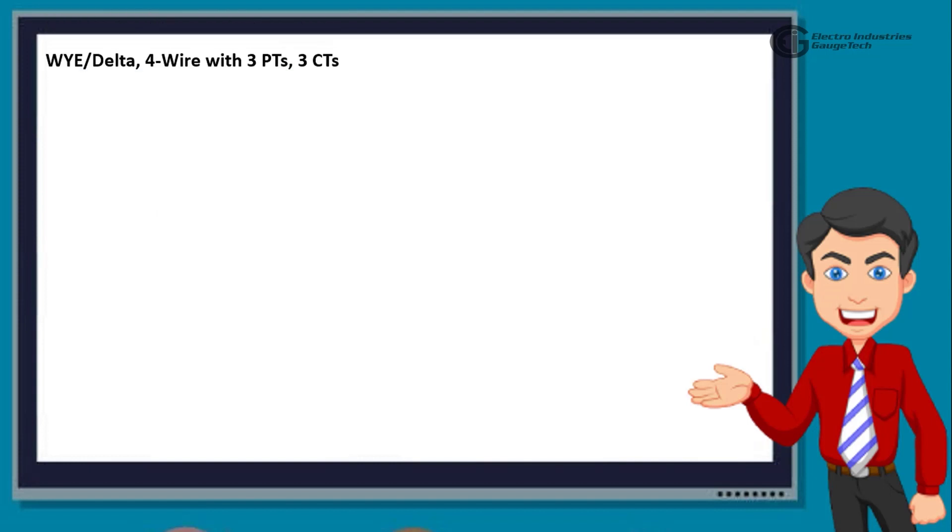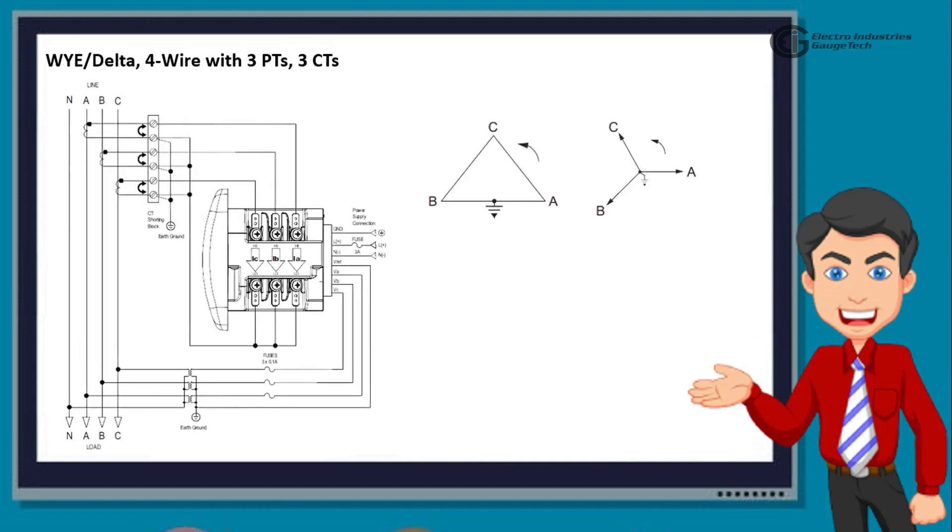Next, we have Y-Delta, 4 wire with 3 PTs, 3 CTs. This diagram shows the 3 phase, 4 wire Y-Delta with PTs, 3 element system. In this case also, when using this wiring, select 3 L Y from the Shark Meter's front panel display.